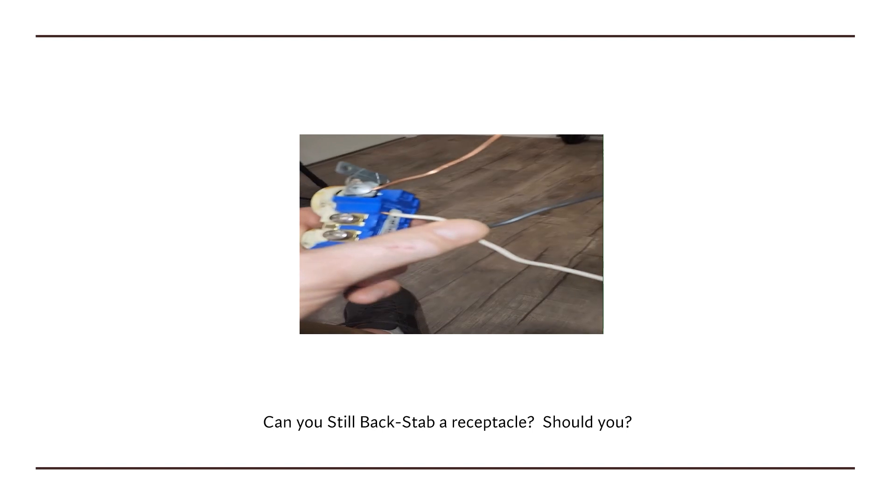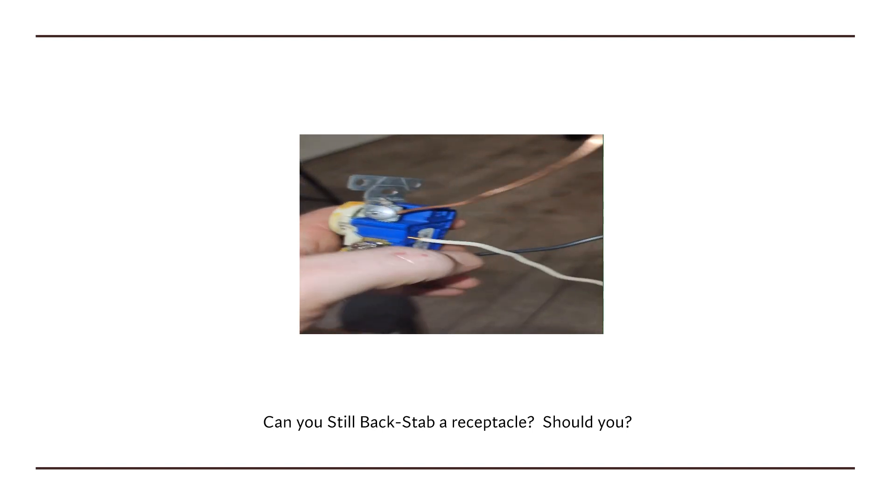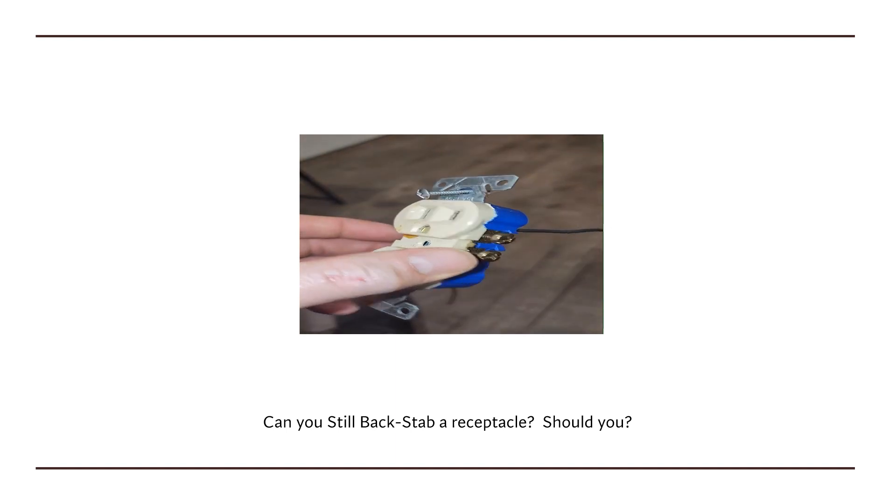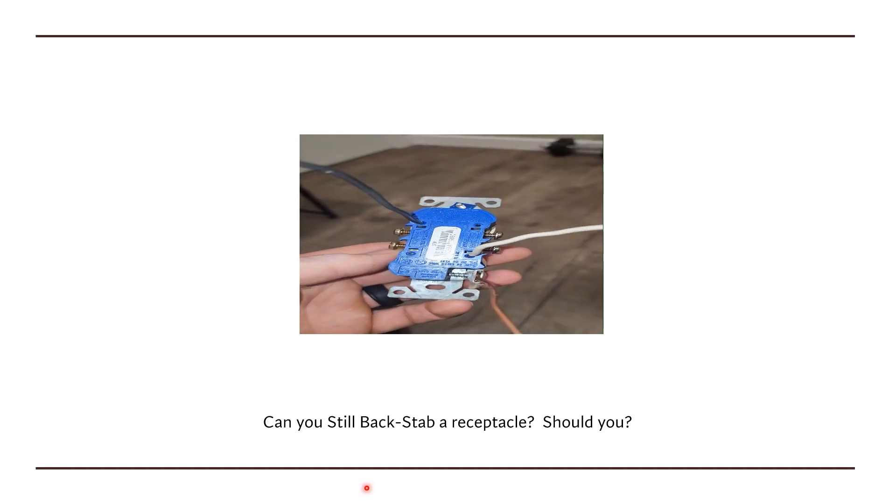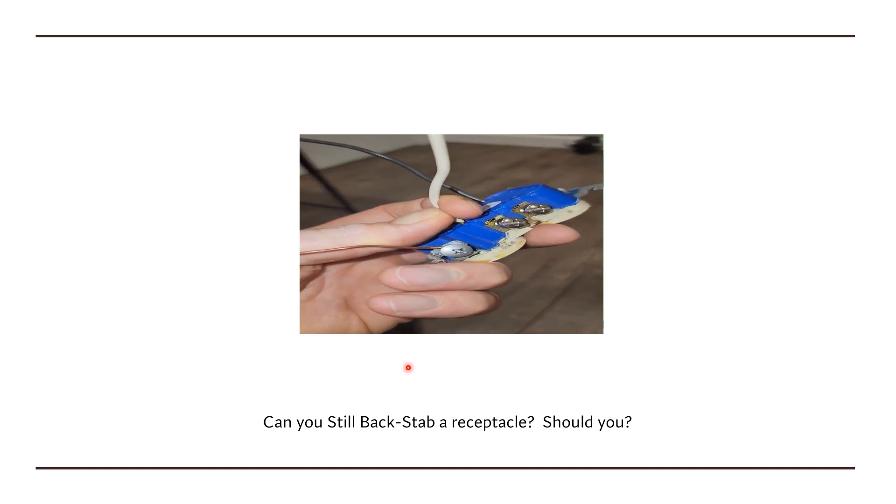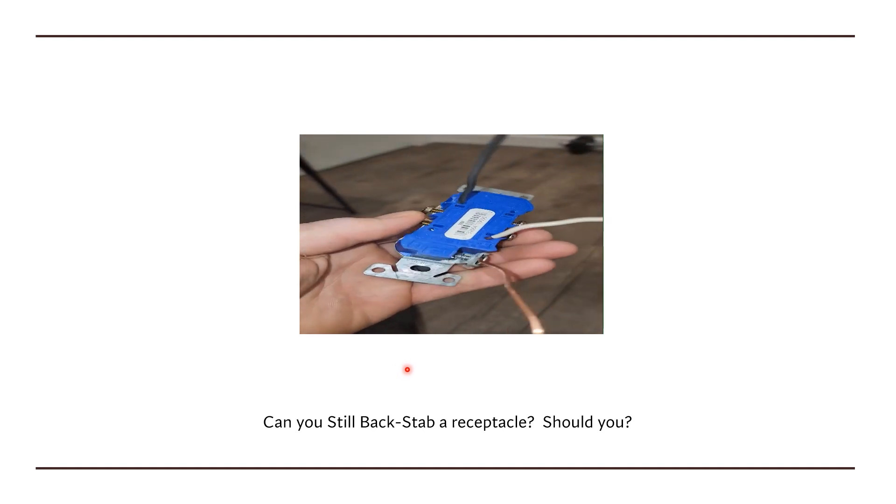So depending on what device you have, yes, it's still legal today. You can still do it, but the biggest thing that we have to watch out for is right here. We have to make sure that we are using it according to its listing. And this is one of the most dangerous things of the original backstab receptacles.